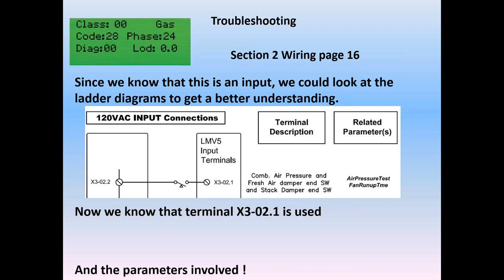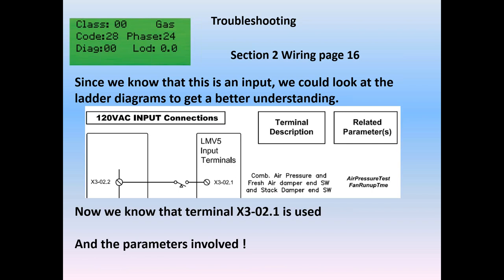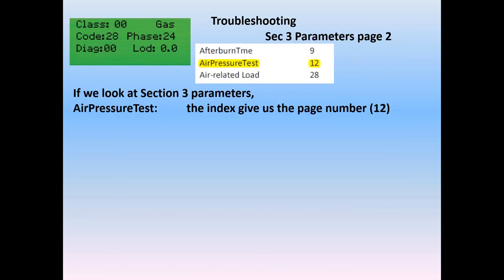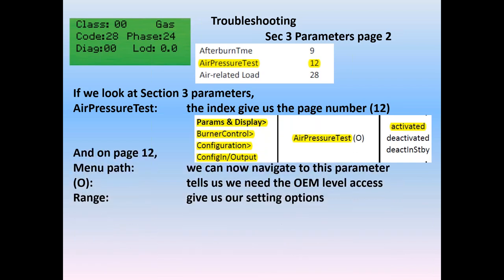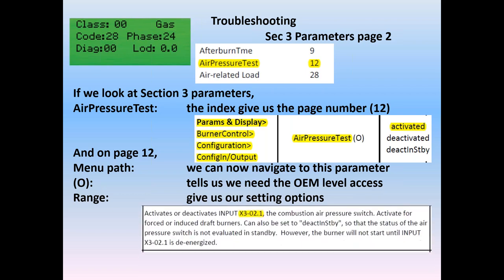Now we know X302.1 is used and the parameters involved in diagnosing the fault. If we look at section 3 parameters — since we know the parameter name is called air pressure test — the index tells us to go to page 12. When we go to page 12, we have a menu path. We can simply go to the AZL: parameter display, burner control, configuration, configure input/output, and we see the air pressure test parameter displayed. The 'O' on here tells us we have to be logged in at the OEM level to access this parameter. The range gives us our options: activate, deactivate, and standby — and a description giving us complete detail on how those parameters work.